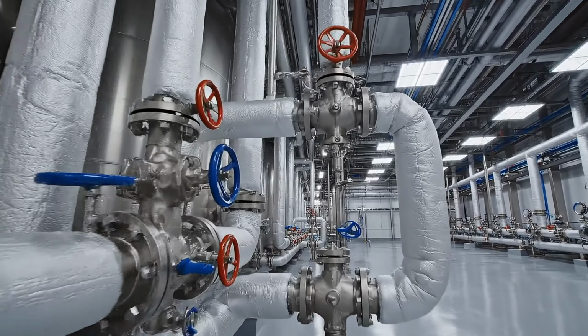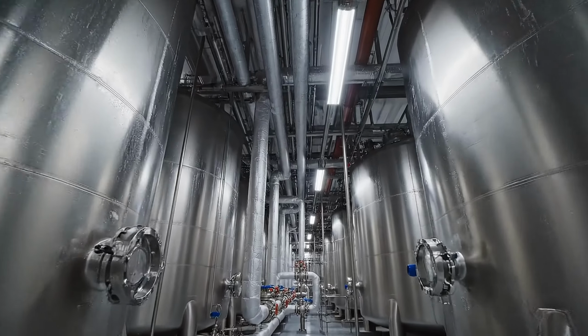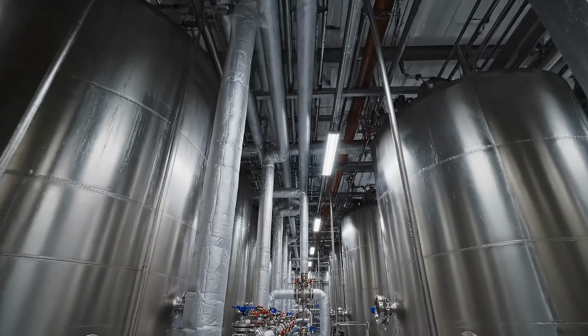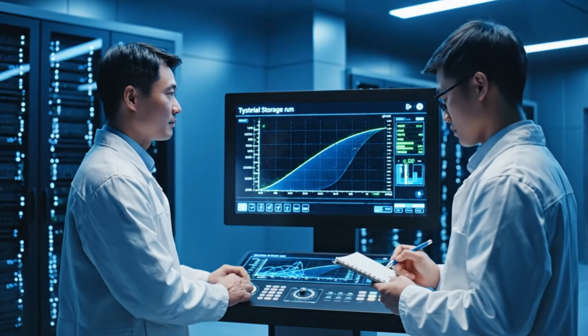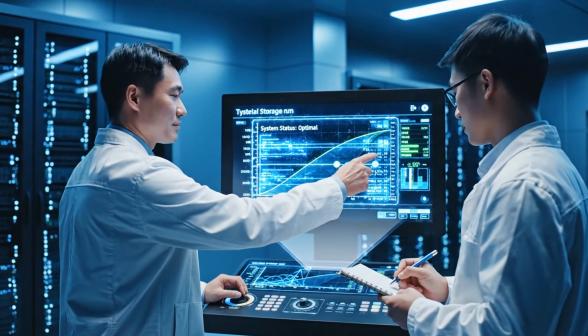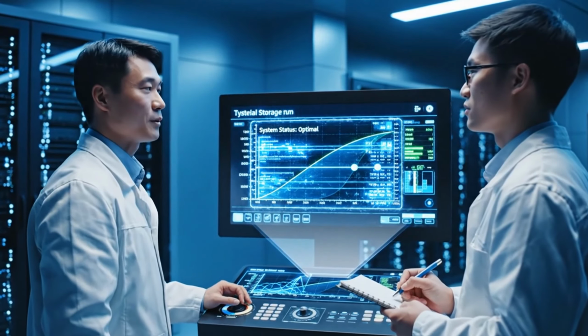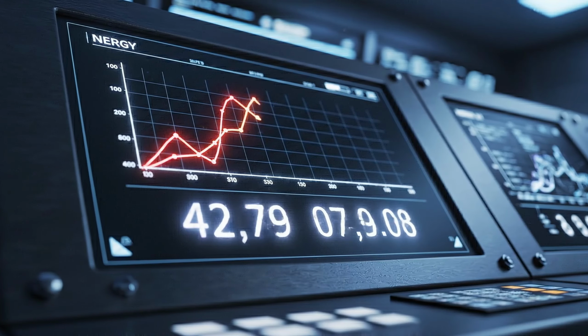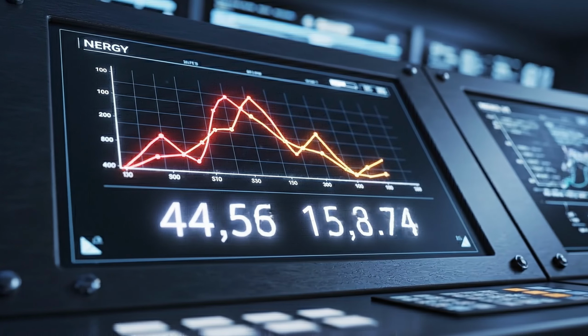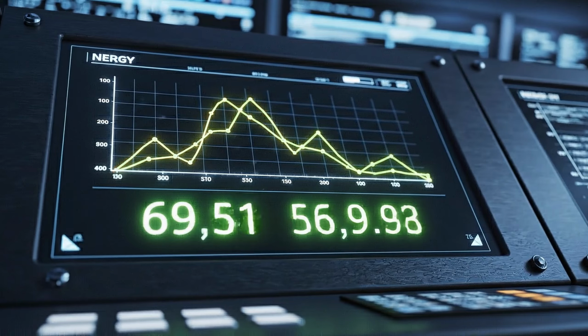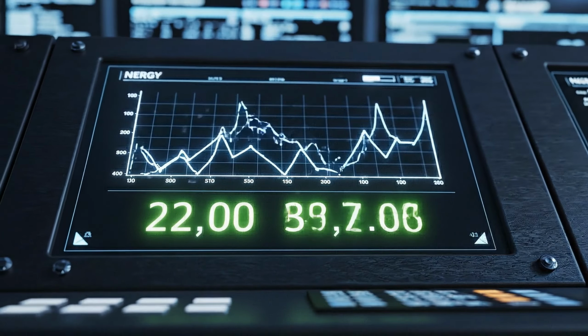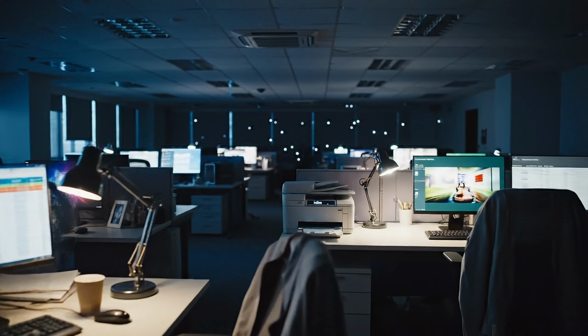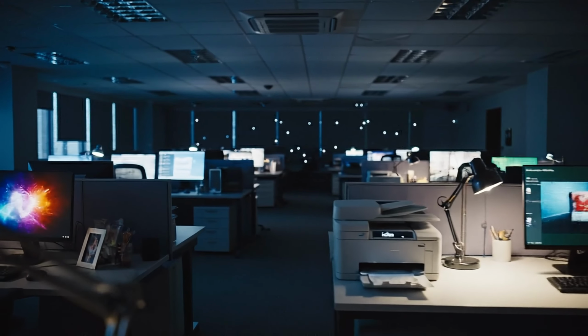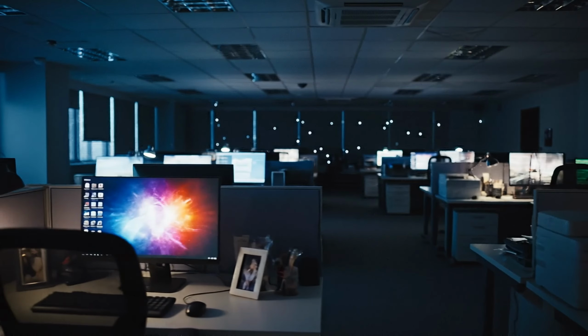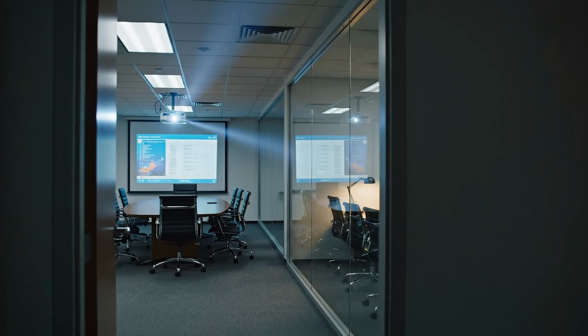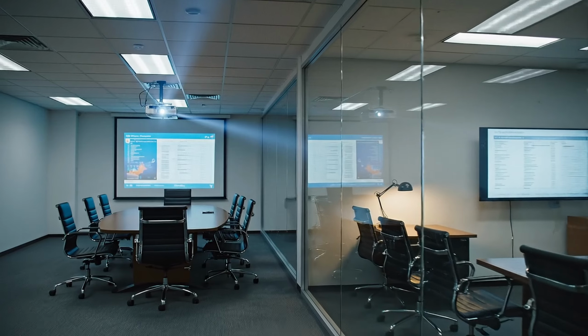But the engineers went further. They introduced a thermal energy storage system. During off-peak nighttime hours, when electricity is cheaper and the grid is under less strain, the system runs the chillers at full capacity, not to cool the building, but to freeze enormous tanks of water into ice. Then, during peak daytime hours when cooling demand is highest, that stored ice is used to supplement the chillers, dramatically reducing the peak electrical load. The building essentially banks cold overnight and spends it during the day.